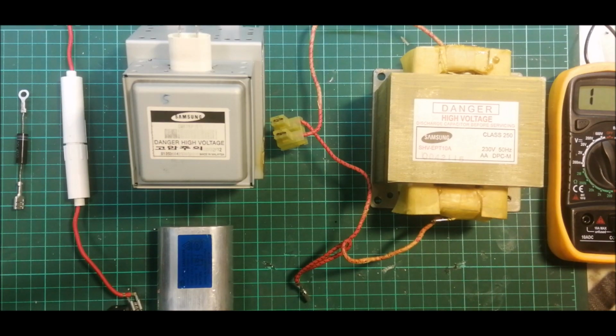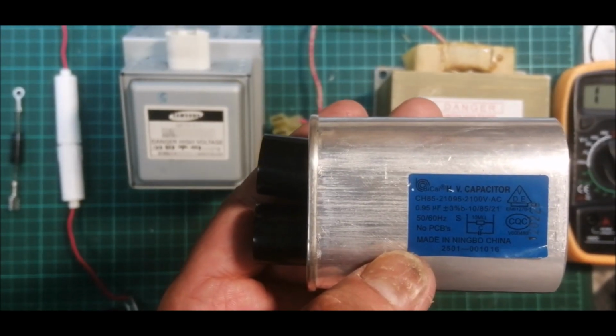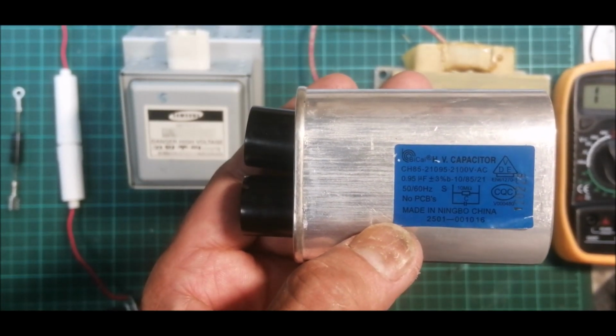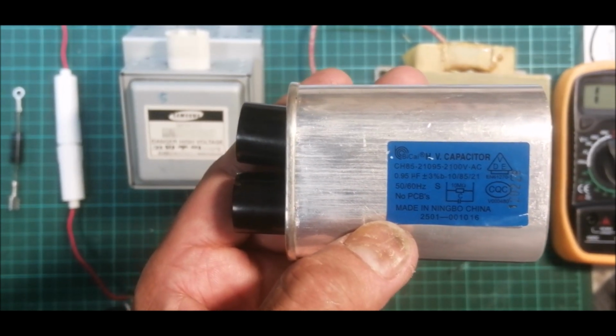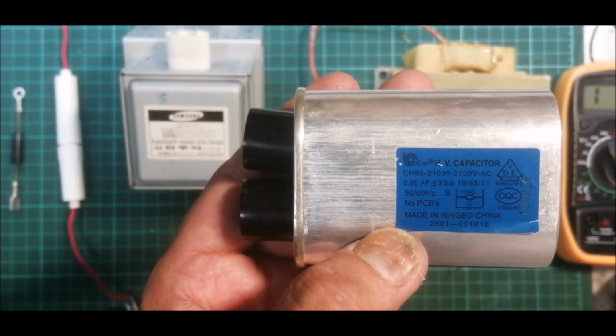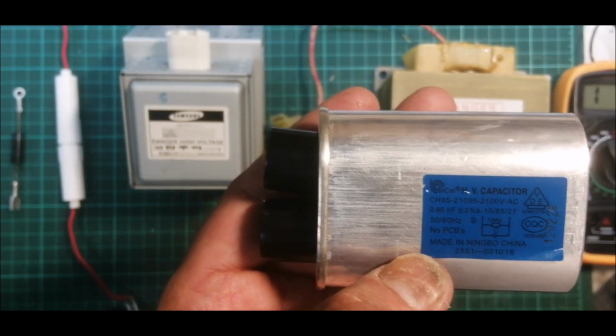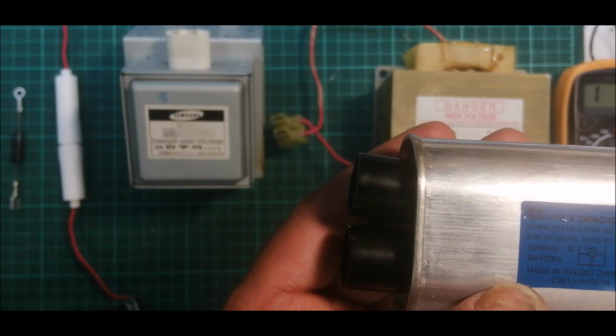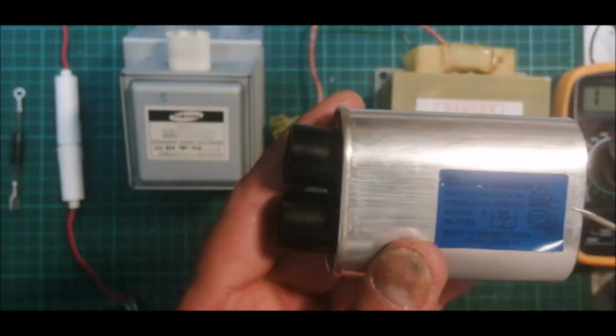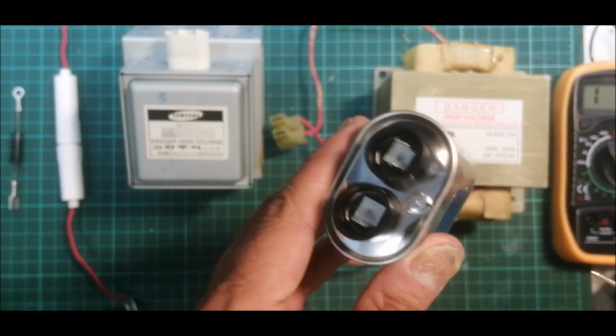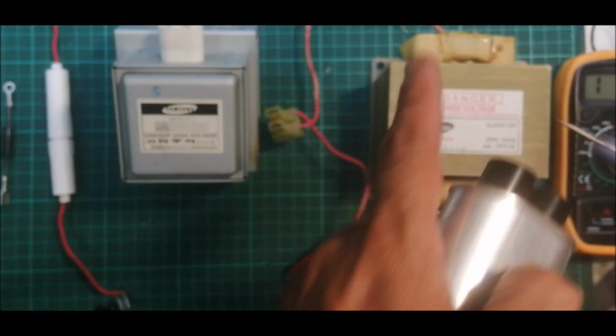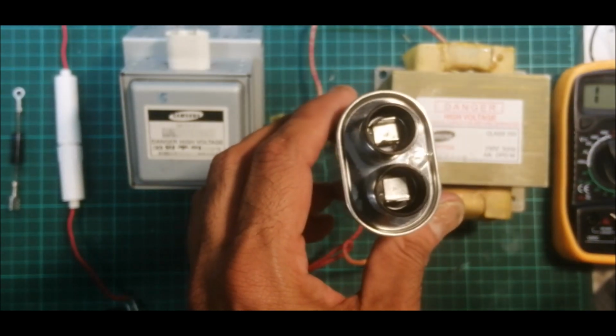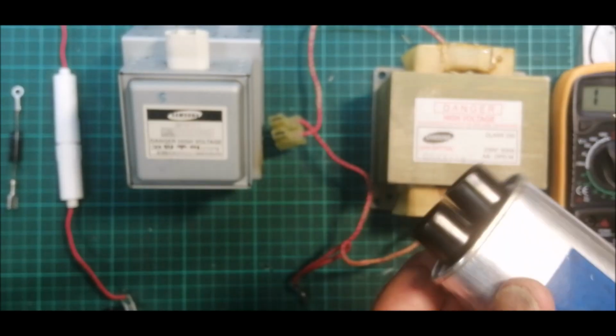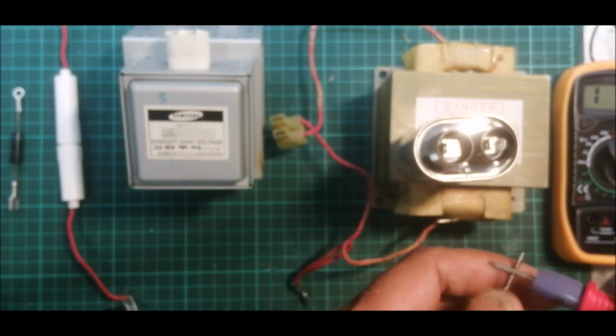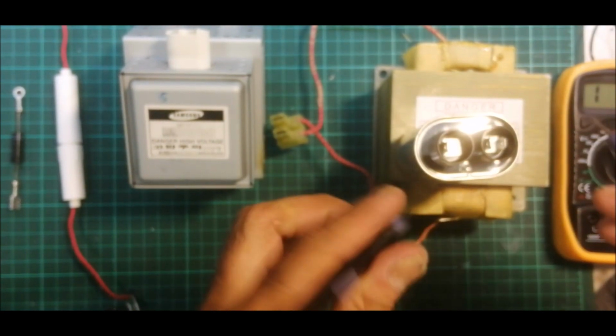So now we will start with the capacitor. This is a 0.95 microfarad capacitor, plus minus 3%. It is a high voltage capacitor. It's a 2100 volt. You can store AC current inside here. So make sure to discharge this capacitor when you want to take all this component out, including this guy. Okay. So now, how to check to see the faulty is just take the continuity, put at the both probes of it.